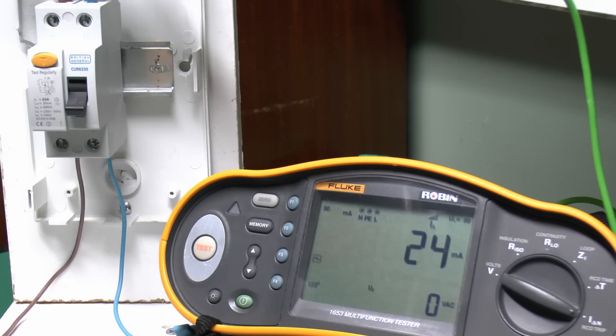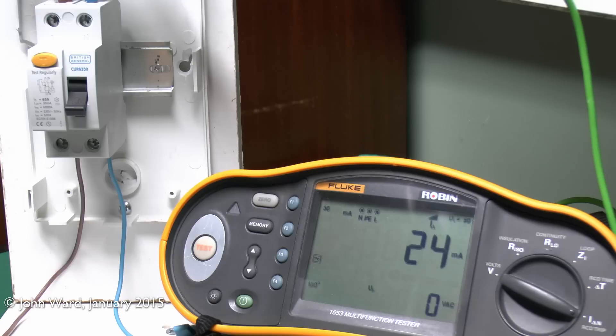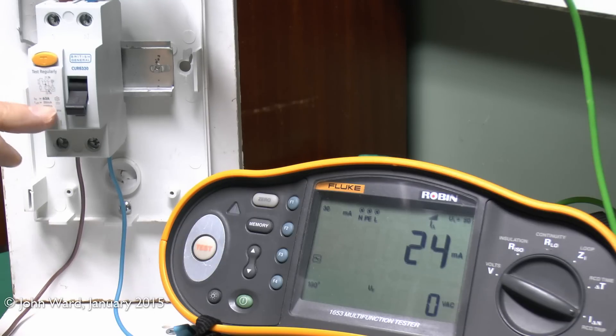Most test reports that you would fill in don't actually have a place to complete this part, but nevertheless, it's a good idea to actually do this test, certainly on a new device, because it's useful to make sure it does actually trip at the current specified.